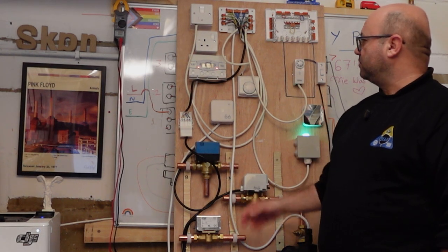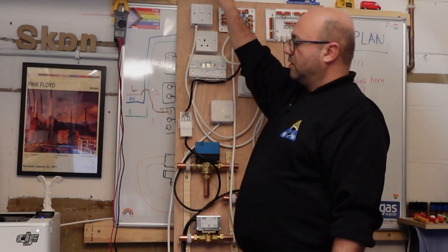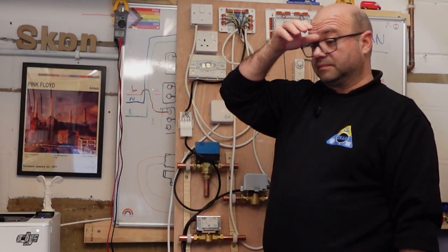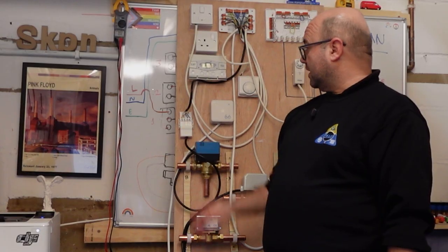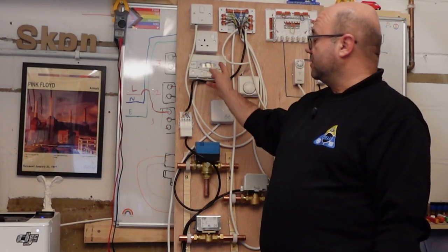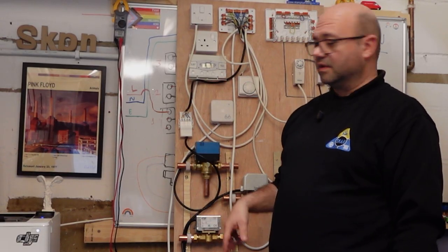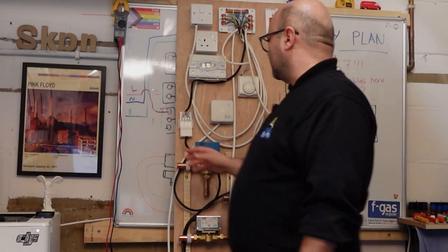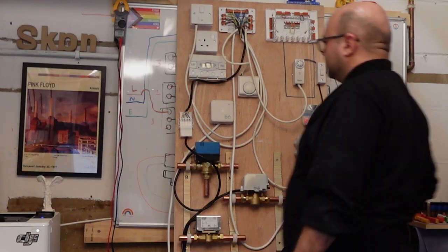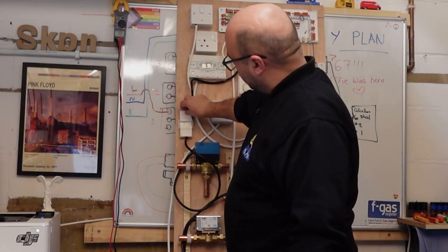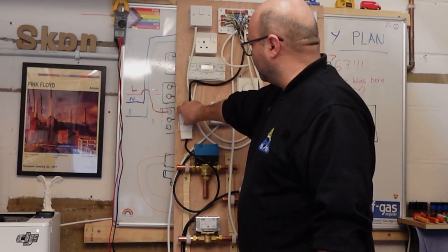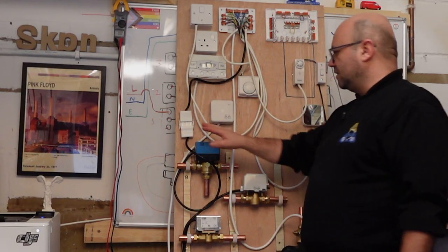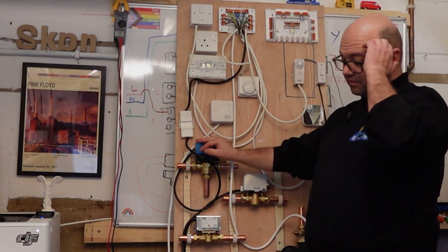But from my experience, just to let you know, when that happens, regardless of what the timer says, you see different figures here. So in this case, everything is fine. So we put back the cover. It's okay. But if we don't see those figures, 9 to 10 times the problem is the 3-port valve.